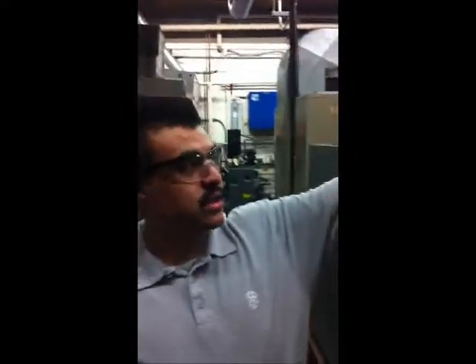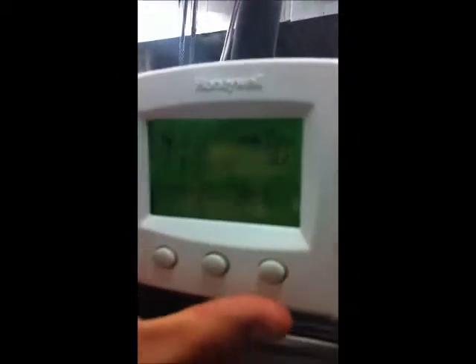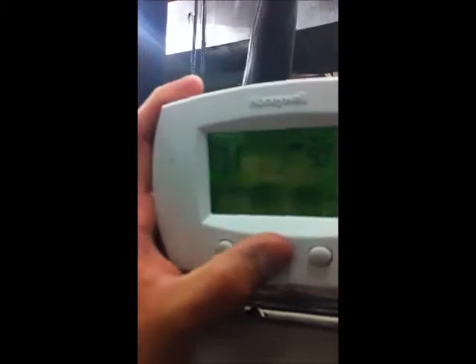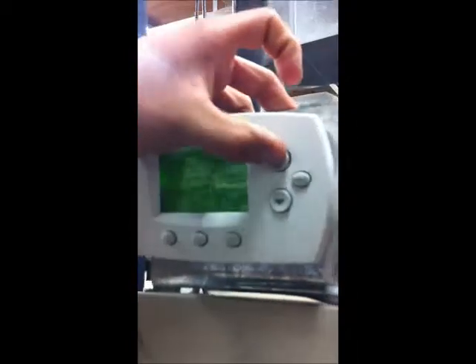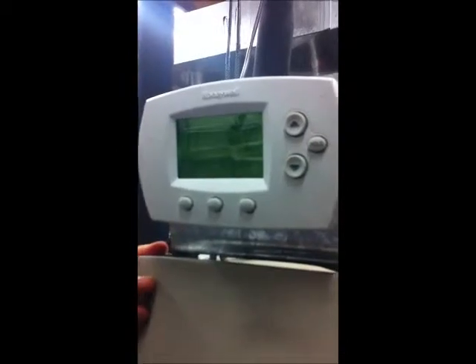Okay, so here we have the thermostat. It's a Honeywell thermostat. We're going to make sure that it's getting power. So we're going to go ahead and switch it to on, into emergency heat, and then we're going to turn the fan to on. And then there we heard the contact click. We have it set at 90 degrees Fahrenheit.